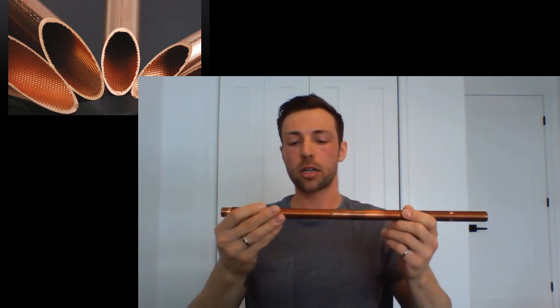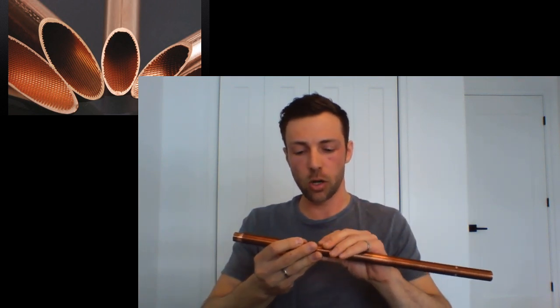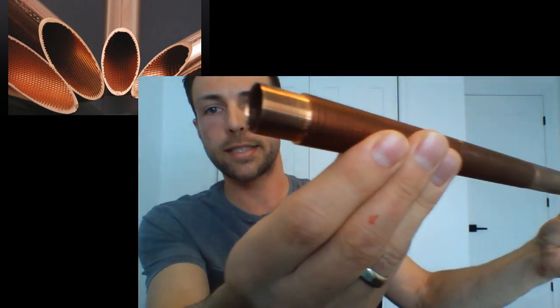Second thing is that they are mechanically enhanced. What that means is that while the tubes are made, they're gonna have small grooves. It's not fins, it's just really small grooves that are carved inside the material. You see on the picture there at the top, it can be internal or also external. So here you see on my camera, I don't know if you can get a good view of it, but you see that that is a clean section, straight without anything, and here are all the grooves that are on top of the tube. You can have tubes which have both, so they have internal and external, or just one or the other. These grooves help to enhance the heat transfer.